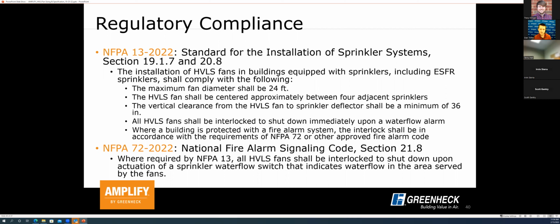So there are a lot of requirements here. The maximum fan size shall not exceed 24 feet. That's why, for the most part, that's the largest available size of an HVLS fan in our industry. The fans have to be centered between 4 adjacent sprinklers so that, again, we're not directly below a sprinkler and impeding its flow. We need to have a minimum of 3 feet of vertical clearance between the fan blades and the sprinkler deflector to make sure the blades are not impacting flow of that deflector. And the fan has to be interlocked with the fire alarm system to shut down so that we're not promoting the spread of fire in the building by adding air and airflow to that fire below the fans. So a lot of requirements there, but very, very critical for most applications that have sprinklers in the building.